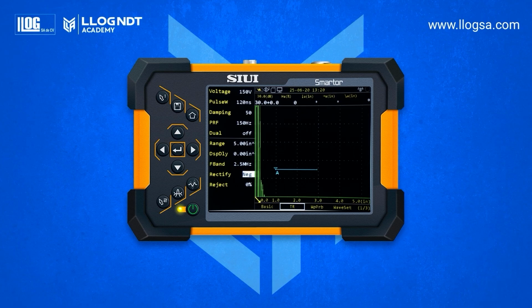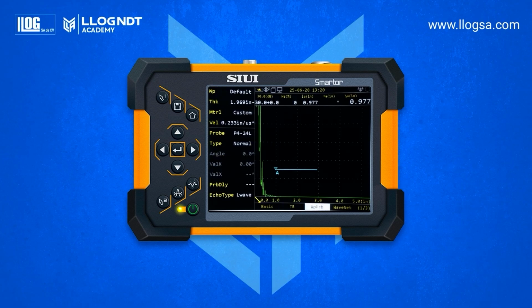Rectification, full wave. In the Part/Probe submenu, set the following. Piece thickness, 1 inch. Material velocity, 0.2320 inches per microsecond for longitudinal waves. Transducer model. In this example, we'll use P2.5 to 20L.